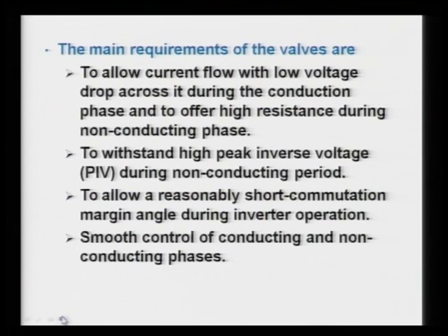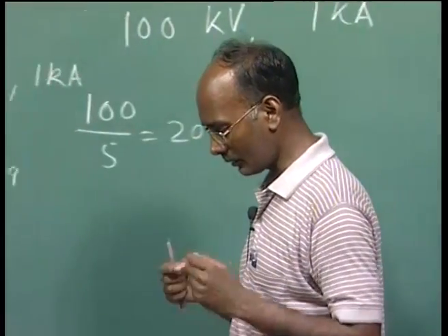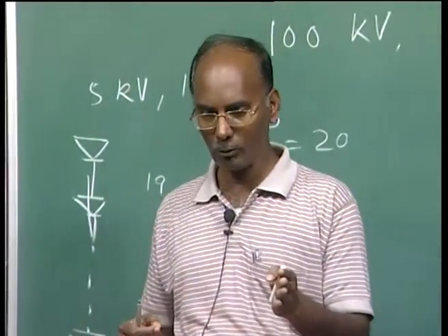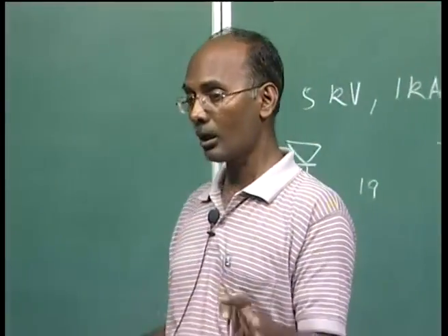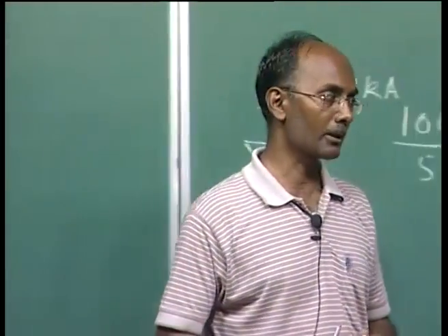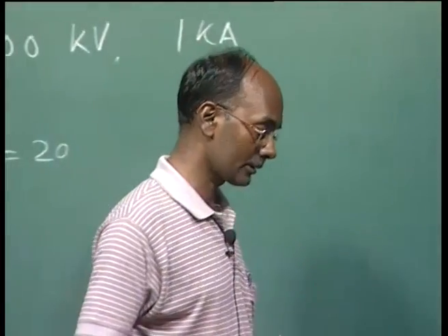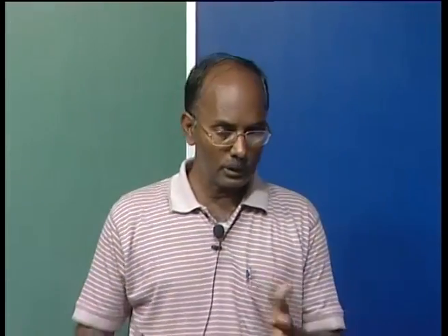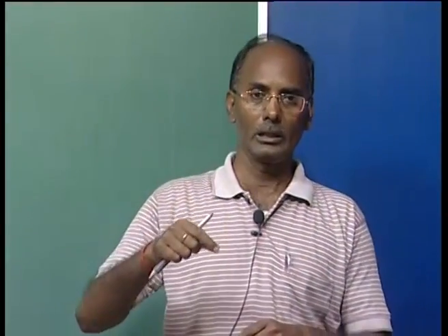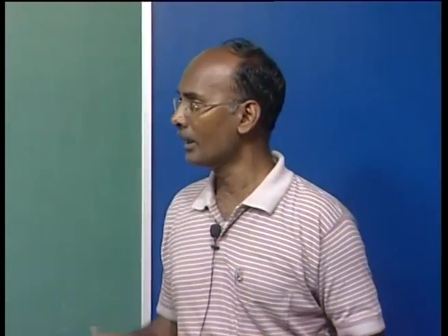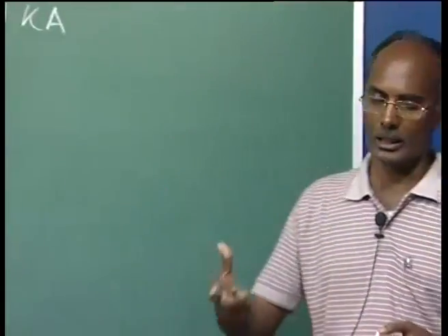If you are making the converter, as you know, there may be various types of converter conduction modes. It may be 2-valve conduction, 3-valve conduction, or 4-valve conduction. Again, we will see how these modes of conduction of the valves or converters come up. During that time, if two are working, the remaining will experience the reverse voltage, and it should have the peak inverse voltage capability. Otherwise, what will happen? This thyristor or your valve might get damaged.